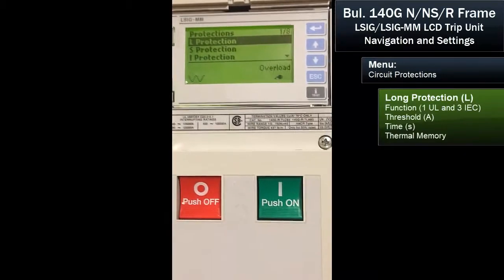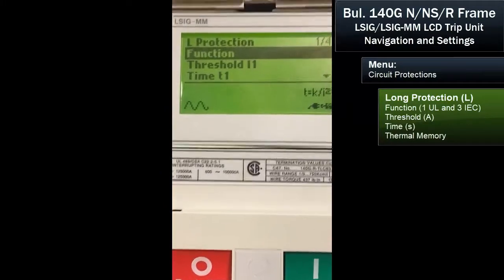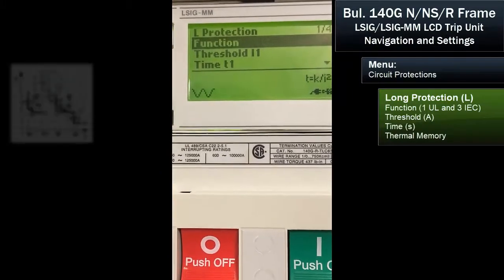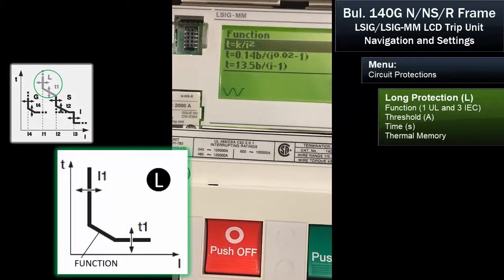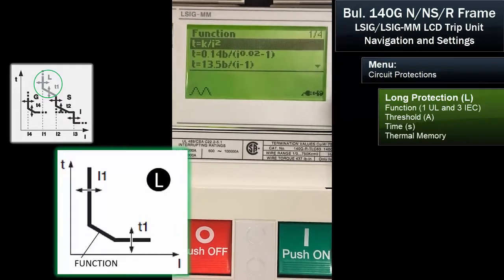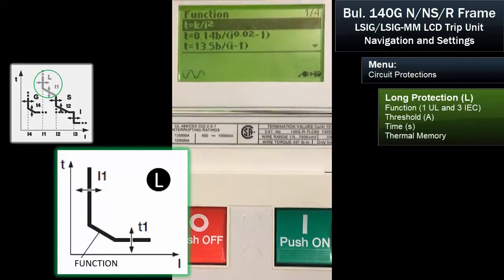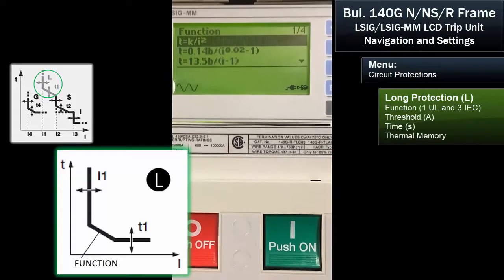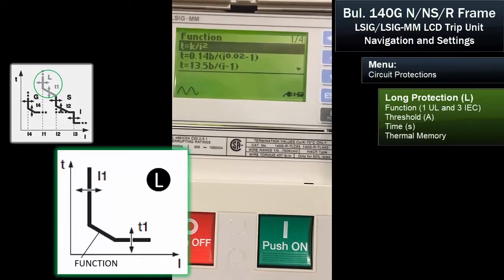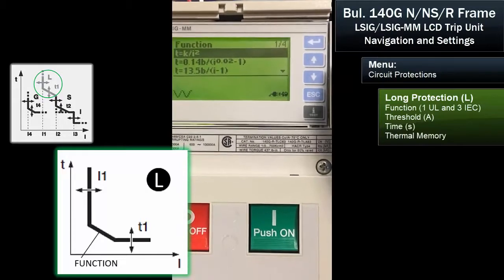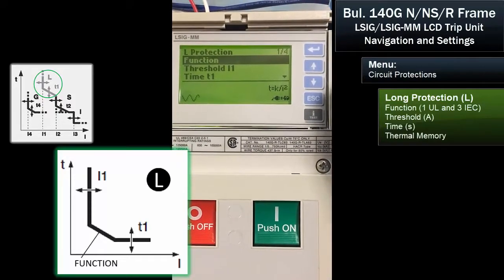Starting with the long protection — the first submenu is functions. We'll hit enter. We want to use the inverse time delay, so that's k, where time equals k divided by current squared. It's an inverse time. I'll hit enter to select that — it's a standard protection.